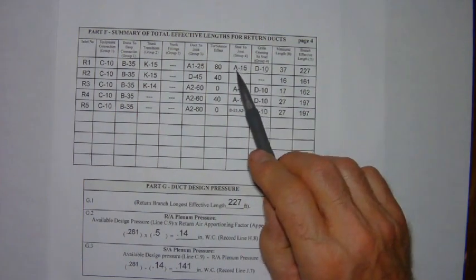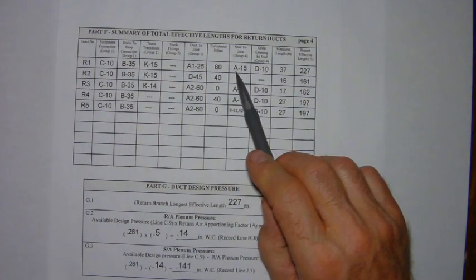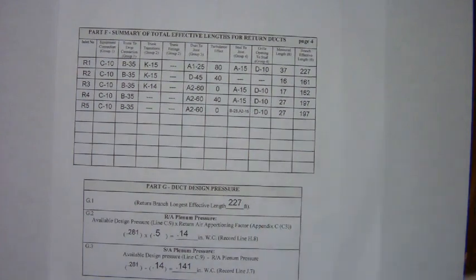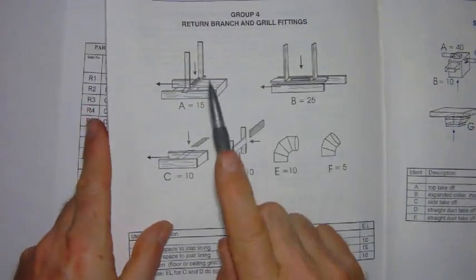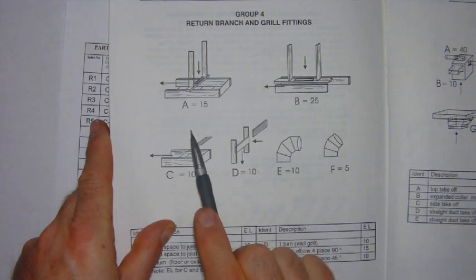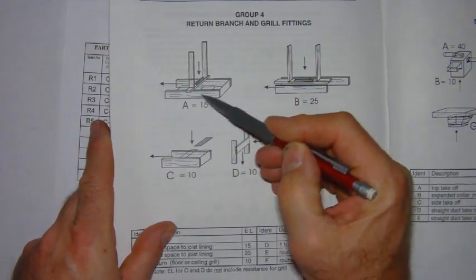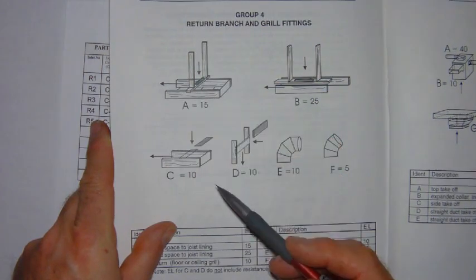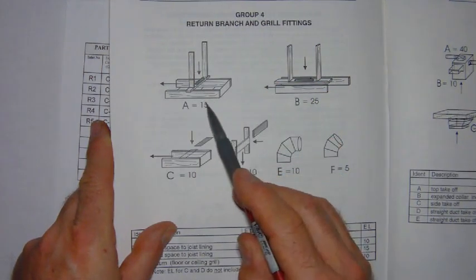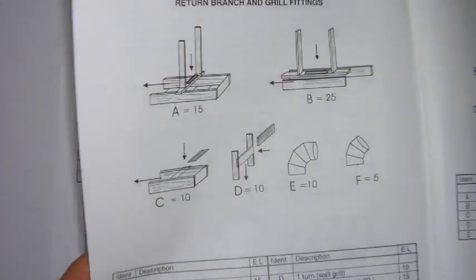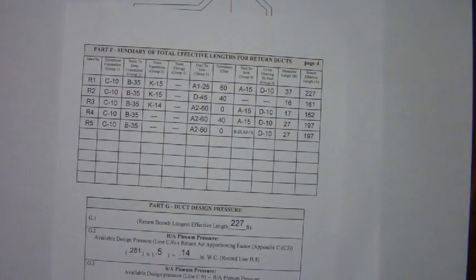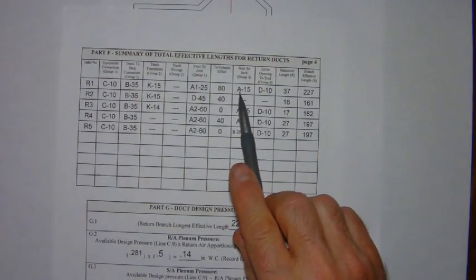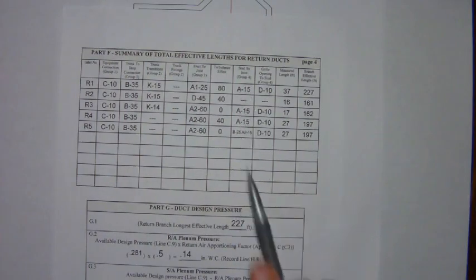And so we've got one A fitting. It's a type A fitting which corresponds to this one because our partition is perpendicular to the floor joist. The air is coming straight down, makes a nice easy turn. So we need to account for 15 feet of equivalent length. And so that's the A is the fitting identifier and 15 is the attributed equivalent length.